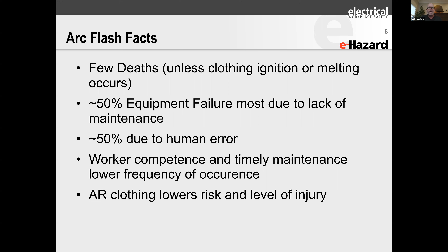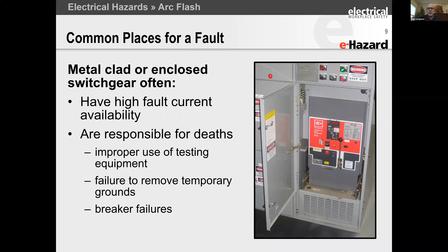So where do these incidents happen? I've done 200 accident investigations in the US, one in South Africa, and one in New Zealand. In doing those investigations, I found one of the most common places for workers to be really hurt is working in metal-clad switchgear, primarily in racking it in or out. There's no shock hazard here, but there's a possibility the stabs are misaligned or broken, or that there's a rodent or something inside, and that can cause the equipment to explode. That's a very common place for people to be hurt.